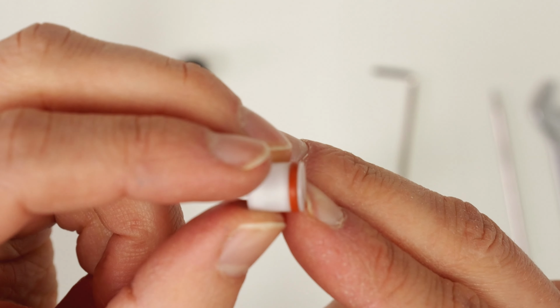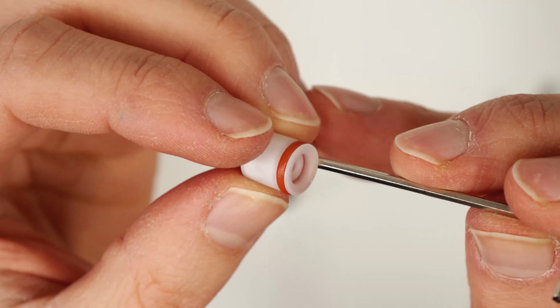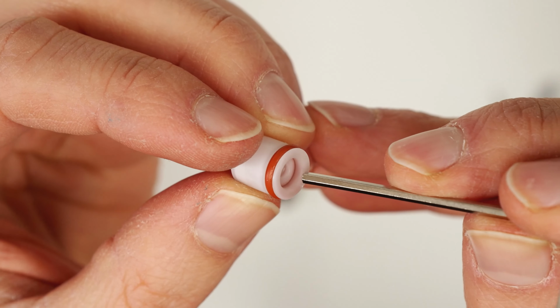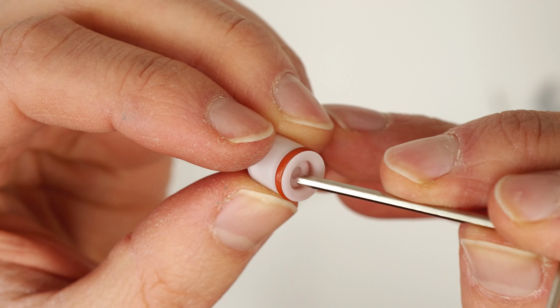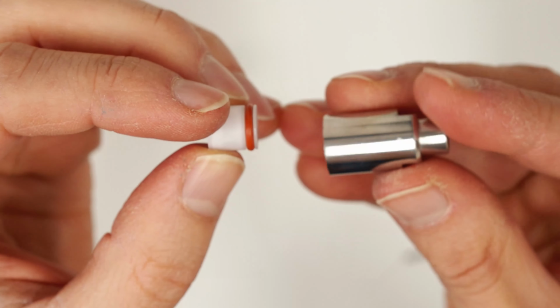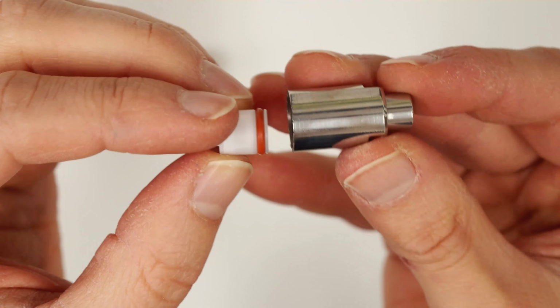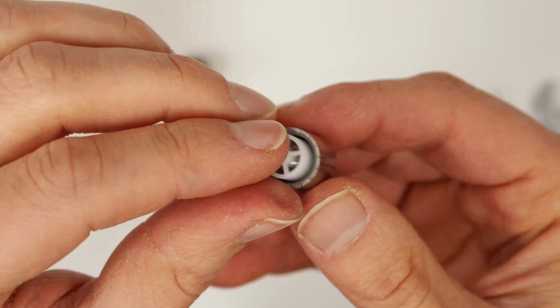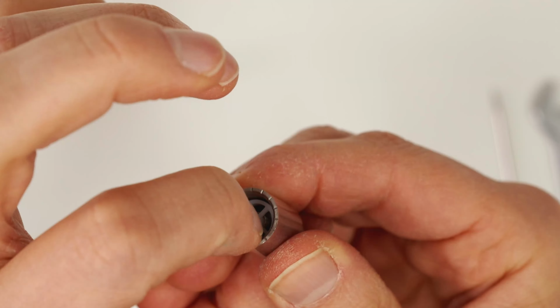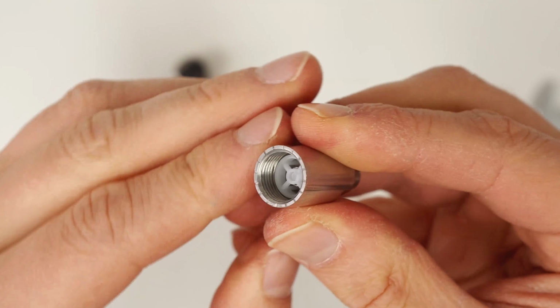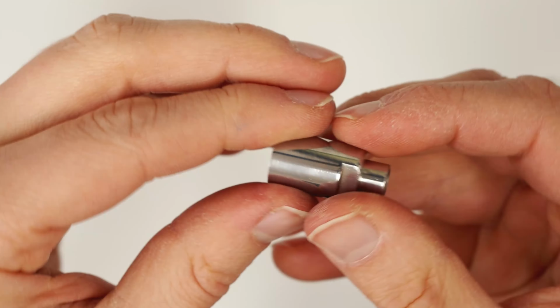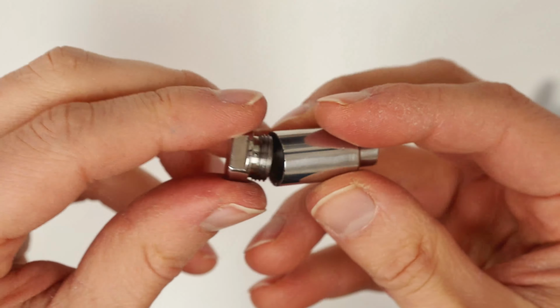When installing the new check valve, pay attention to the direction. If the gas comes from here, the valve opens. In the LCS, the gas comes from above, so the valve must be installed in this orientation, with the red ring first. After that, reassemble the nozzle.